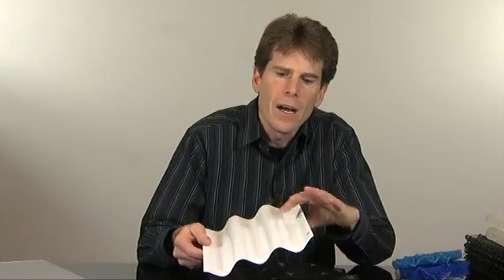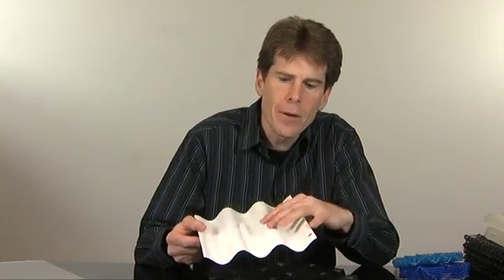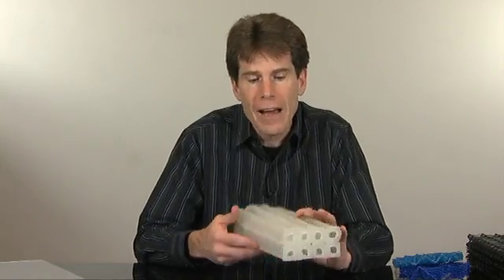Taking these in order of fouling, the parallel corrugated plate is probably the least fouling of the bunch. The plate system with a regular shape built up into a pack fouls more than that. And the next most fouling — the one that fouls more than that — would be what they call a VTC coalescer.